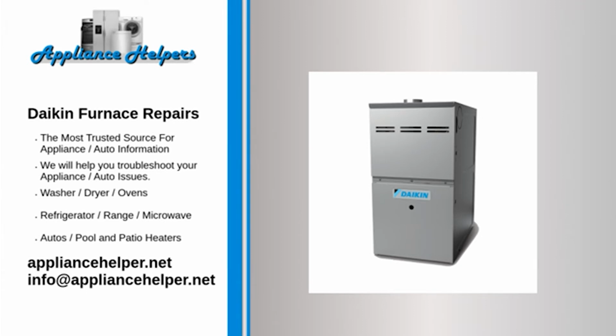The furnace won't start if nothing happens when the thermostat is set above the home's current temperature. The most likely causes are these. The furnace switch, located on or near the furnace and looking like a common light switch, is turned off and simply needs to be turned on. Though the furnace might have a short delay before starting, the circuit breaker may be off. And if the circuit continues to trip after it is turned back on, there is likely a wiring short in the furnace.